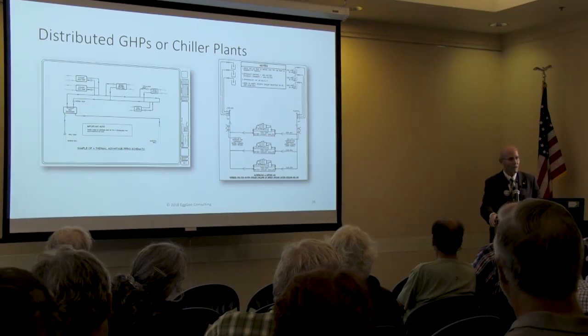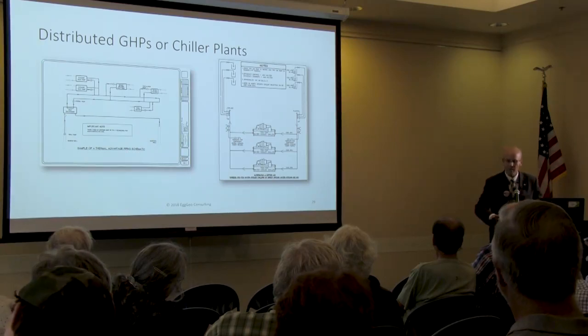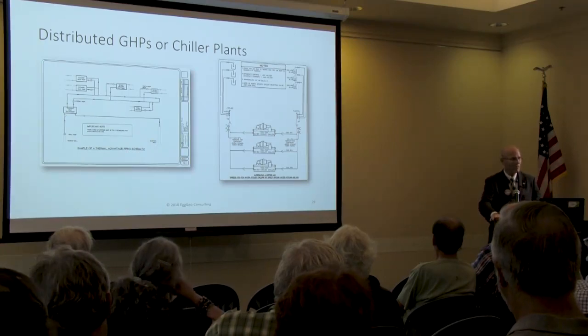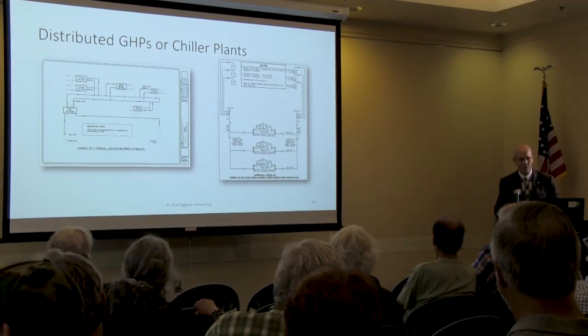So if you don't know what CHP means, that means combined heat and power. What essentially that means is they're burning natural gas to make electricity, and the electricity is feeding different various parts and pieces, and they're grabbing the waste heat off of the exhaust, and that's making more hot water. The fact of the matter is, CHP is probably the best use of natural gas if you have to use it, but the better use is to use the grid, because the grid is green and getting greener, and we're going to talk a little bit more.